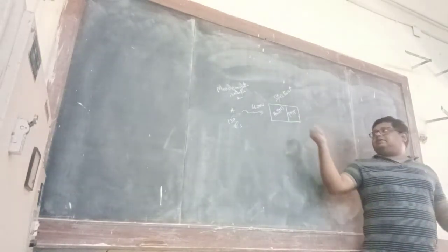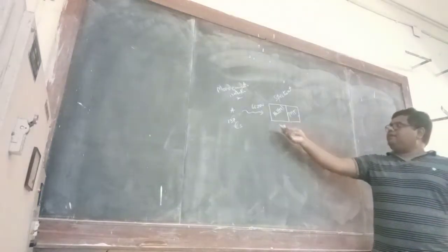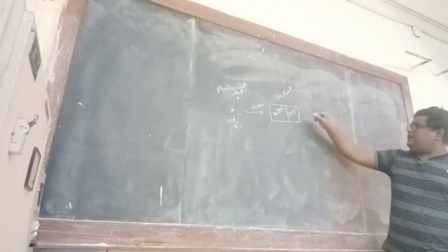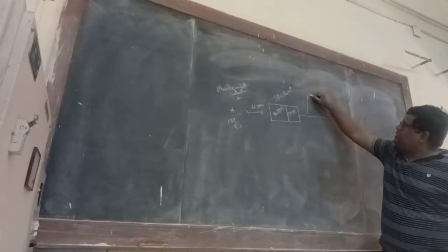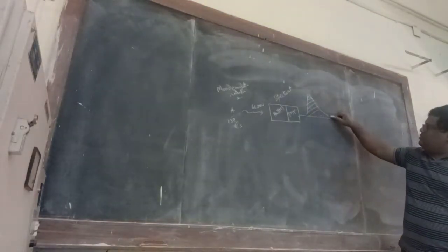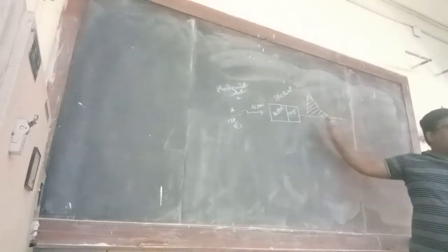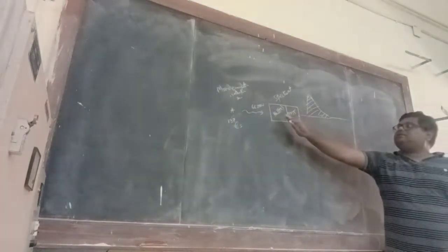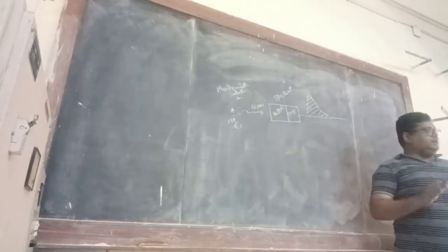A single small energy photon is converted to a large number of, say, 10,000 electrons or so. So effectively we have the conversion of this 662 keV to a large number of electrons through the two-step process. As a result, we have a signal like this. This is the electrical signal. What does this tell me? If this is the background, then the area tells me that this much charge has been collected as a result of the interaction of a gamma ray, which we know from the source is 662 keV, with this detector.